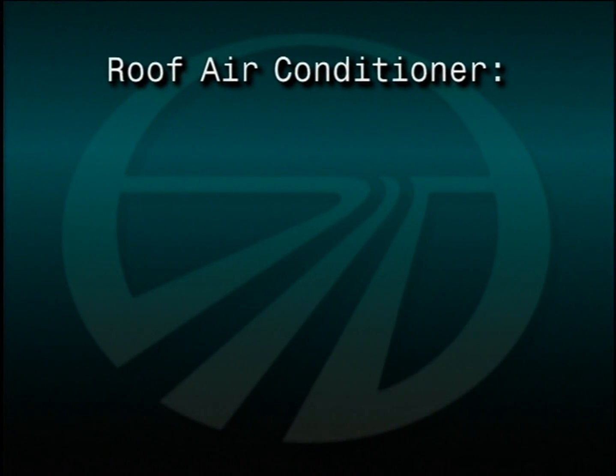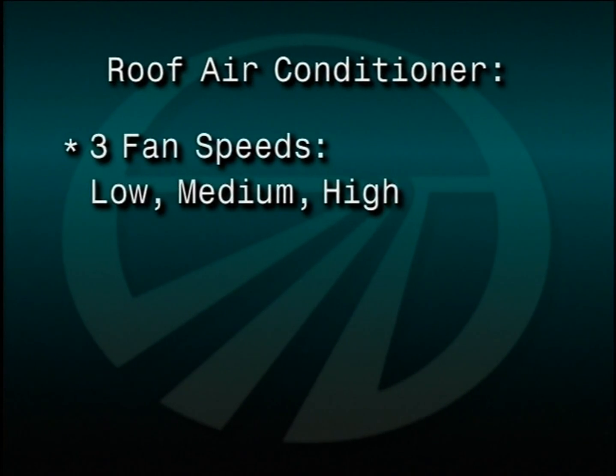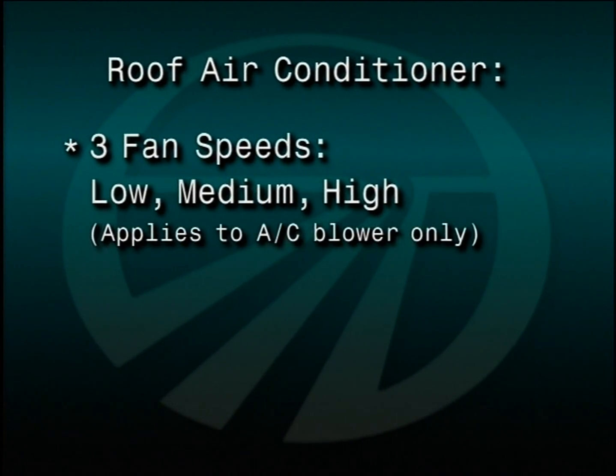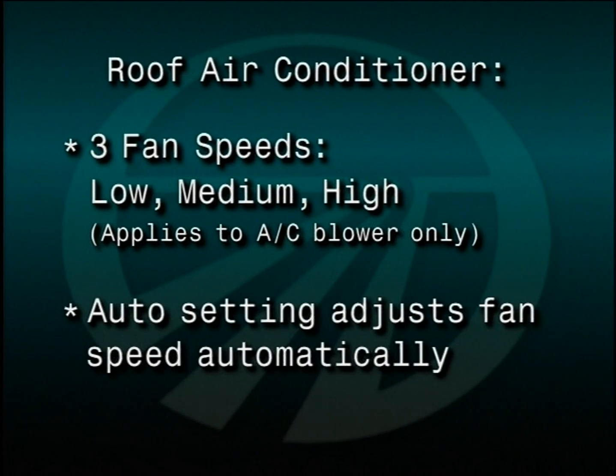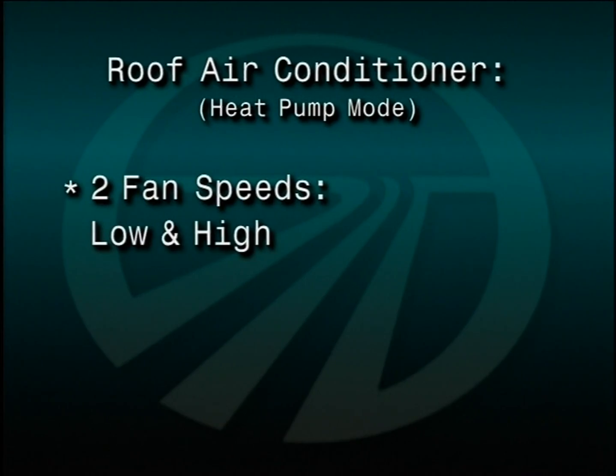The fan button controls the roof air conditioner fan speed. 3 speeds are available: low, medium, and high. Fan speed control applies to the roof air conditioner's blower speed only. Selecting the fan speed auto adjusts the fan speed automatically, depending upon temperature set point and actual temperature in a selected zone. The roof air conditioner will use all 3 blower speeds when auto fan is selected in cool mode. If operating in heat pump mode, only low or high blower speeds will be used.